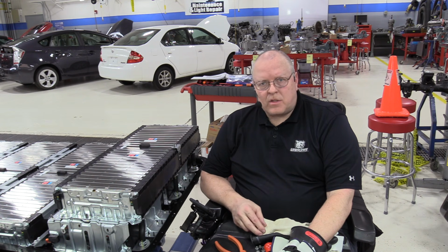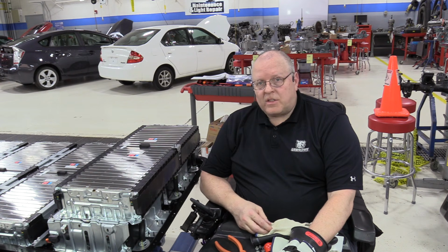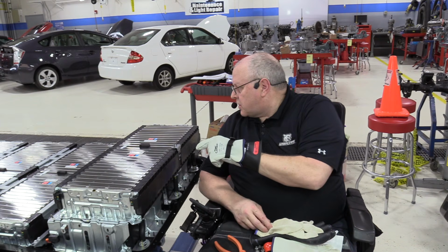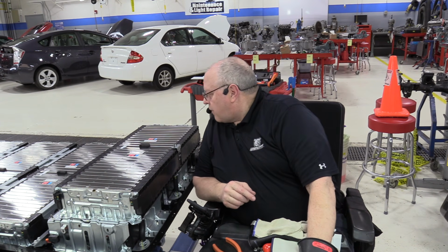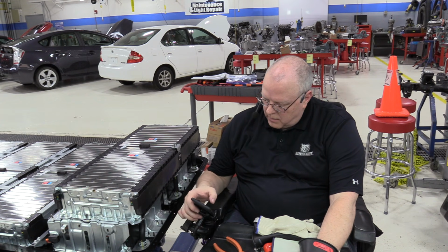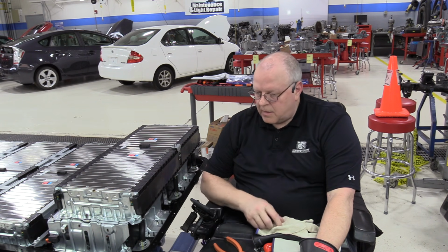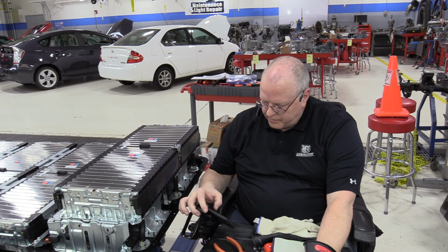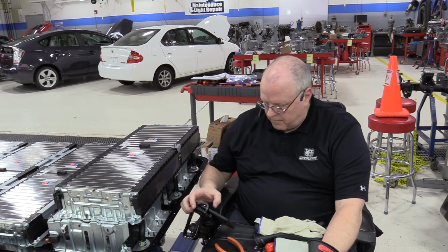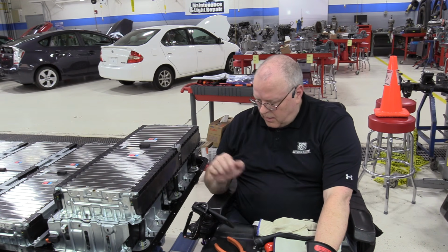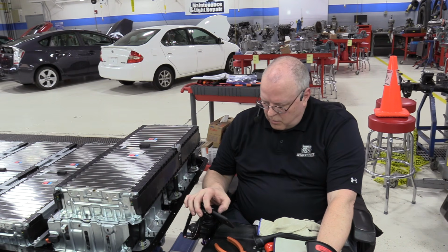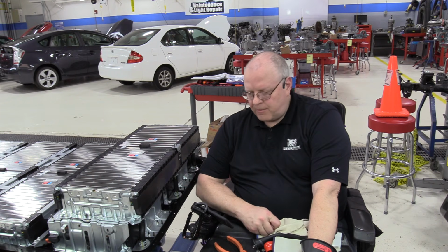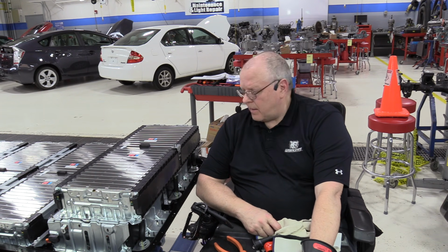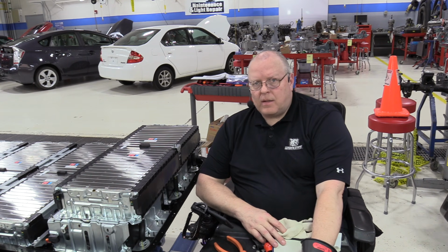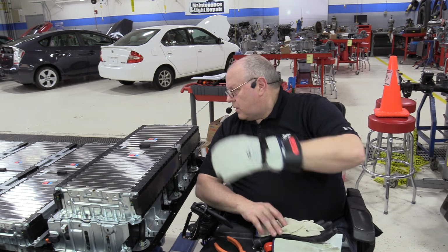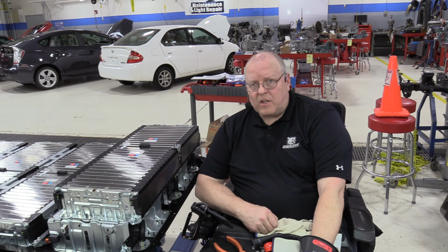That means for those of you who insist this is a 60 kilowatt hour rated battery, the labels disagree with you. So we have 8 battery modules at 5.94 kilowatt hours. 5.94 times 8 gives us 47.52 kilowatt hours. Then we have 2 at 4.75, which gives us 9.5 kilowatt hours. Adding that to the previous calculation gives us exactly 57.02 kilowatt hours. So I don't know where the 60 kilowatt hour rating came from. It's clearly marked as 57 on the cover. You add up the battery modules and it's 57 exactly.